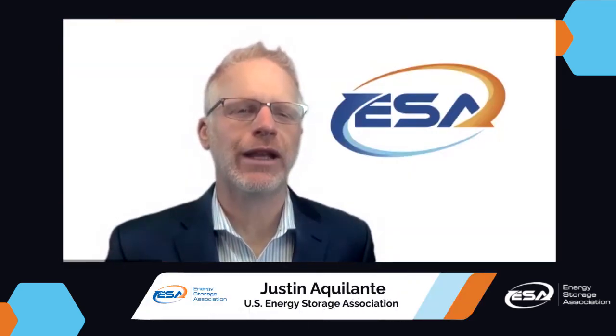What can we do to prevent this all from happening? Yeah, that's a really great question, and one that I field quite a bit from the industry. No one wants to have a fire at their installation or a ground fault occur and it go unnoticed and lead to a disastrous incident. There are a lot of things that can be done. The first and the easiest thing is to make sure that the ground fault monitoring scheme that is being used on the system is properly implemented. You want to make sure that you have a system that is giving you reliable information that you can trust, and then you can take corrective action on.